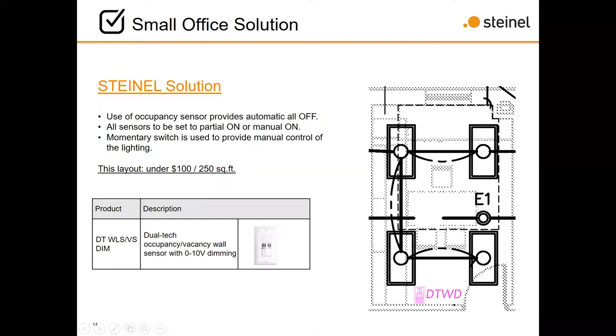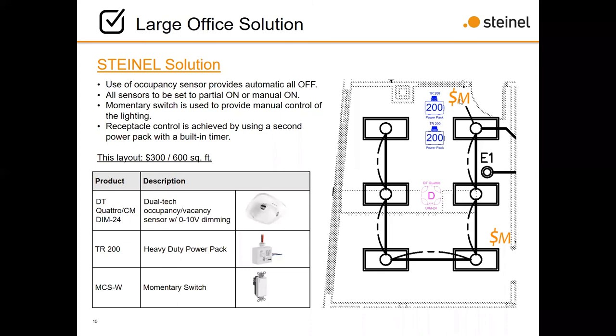In a slightly larger office, let's say 600 square feet, where you've got 6 fixtures in this case, we're going to provide an auto off capability, with user choice of partial on or manual on to be code compliant. We've got, again, the momentary contact switches at the 2 doorways to provide manual override of on/off as well as dimming. And you've got receptacle control, again using 2 different power packs coming off the sensor. The one power pack will control the receptacle, automatically turning on as soon as there's occupancy detected. Basically this setup with 1 sensor, 2 power packs, and a pair of momentary contact switches is probably under $300 purchase price to the contractor. So really cost effective.